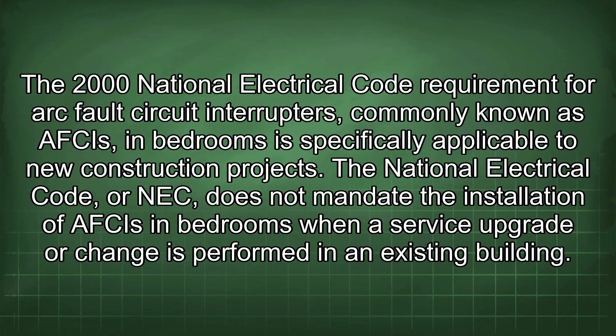The 2000 National Electrical Code requirement for arc fault circuit interrupters, or AFCIs, in bedrooms is specifically applicable to new construction projects. The NEC does not mandate the installation of AFCIs in bedrooms when a service upgrade or change is performed in an existing building.